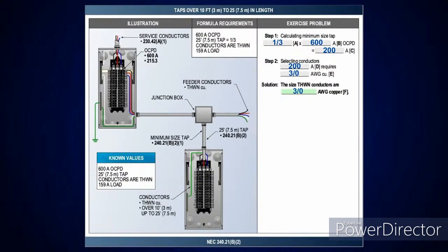Then I go to a 25-foot tap. We're in 240.21B2. I said everything else we take at a third. So I take 600 amps at a third. That's going to give me 200 amps. Once again, I go to table 310.16, 75 C column. Come down. You're going to pick up the next value equal to that. In this case, it's 200 amps. Come across the left-hand side, it's going to tell you it's a 3-aught conductor. So your size THWN copper conductors for this tap will be 3-aught. All right. Then we're going to go to the next one.